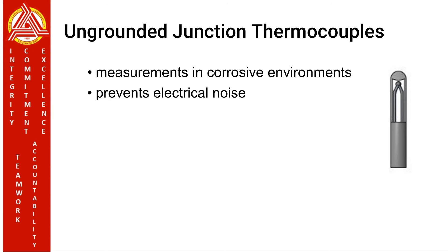Ungrounded junction thermocouples. In an ungrounded probe, the thermocouple junction is detached from the probe wall. Response time is slower than the grounded style. It is usually recommended for measurements in corrosive environments where it is desirable to have the thermocouple electrically isolated from and shielded by the sheath. It also prevents electrical noise from interfering with the signal.